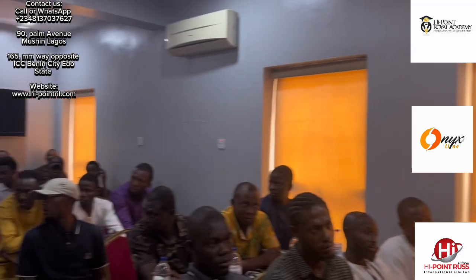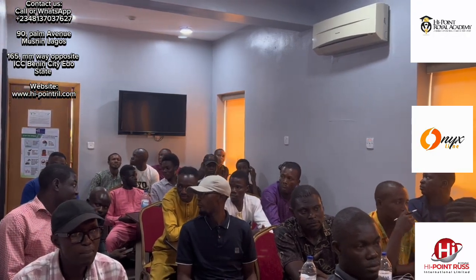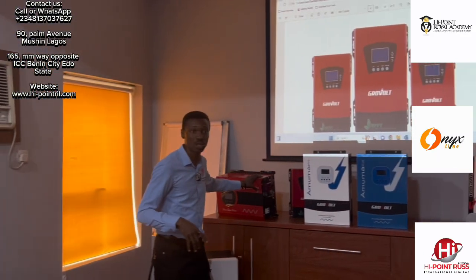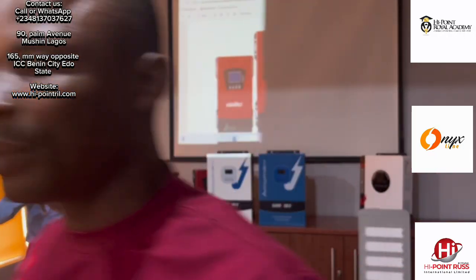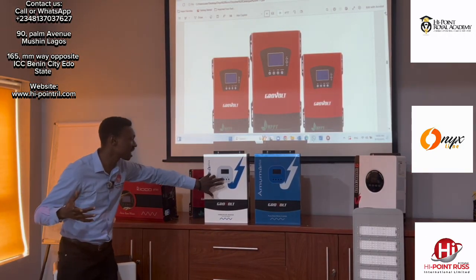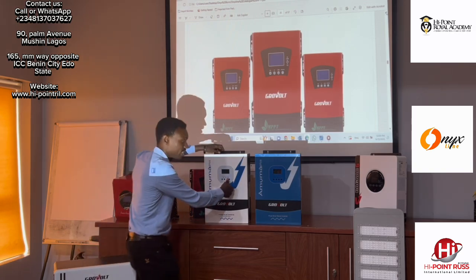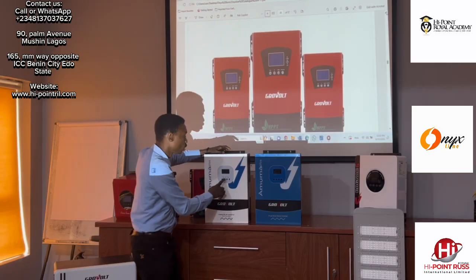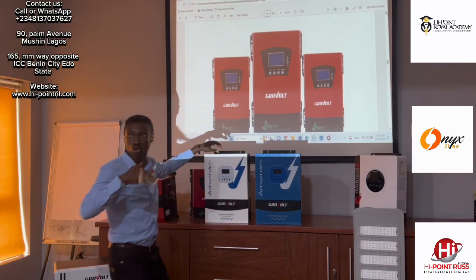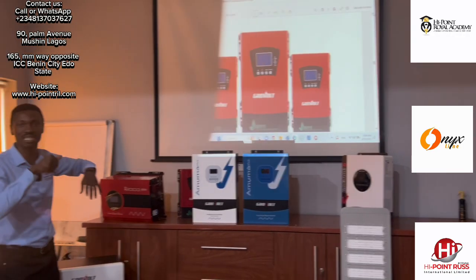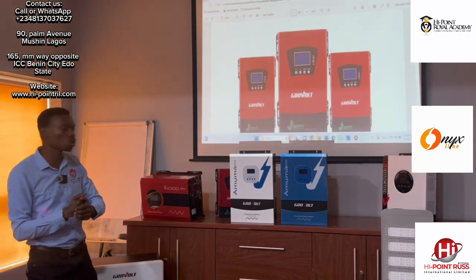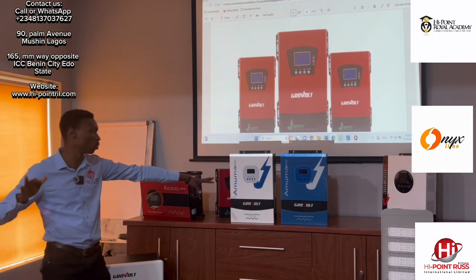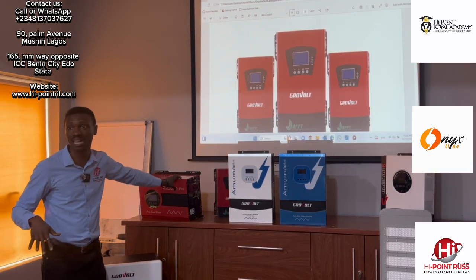Question. Does it have a DIP switch? No. The things that the DIP switch sets, in this one you can set those on the LCD here. Deep switch settings such as the voltage range and the battery cutoff range, you set it. It's like buttons. You long press on the enter, and it will take you to settings, and then you go to settings number 1, settings number 2. Those different setting areas. Then you set the voltage range you want. You set the cutoff. You set the charging current you want. All that is settable from the screen here, unlike the Rico that had the deep switches for it.